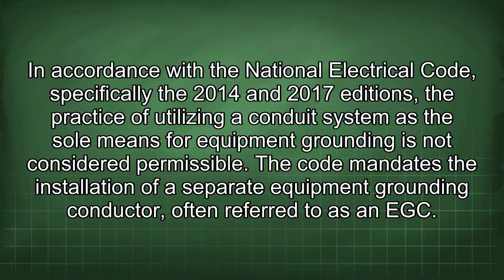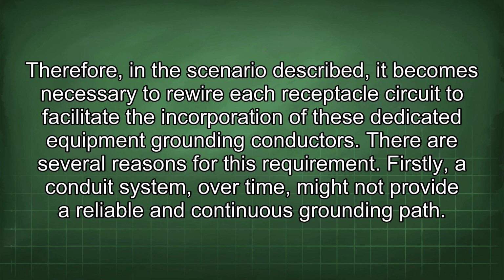In accordance with the National Electrical Code, specifically the 2014 and 2017 editions, the practice of utilizing a conduit system as the sole means for equipment grounding is not considered permissible. The code mandates the installation of a separate equipment grounding conductor, often referred to as an EGC. Therefore, in the scenario described, it becomes necessary to rewire each receptacle circuit to facilitate the incorporation of these dedicated equipment grounding conductors. There are several reasons for this requirement.